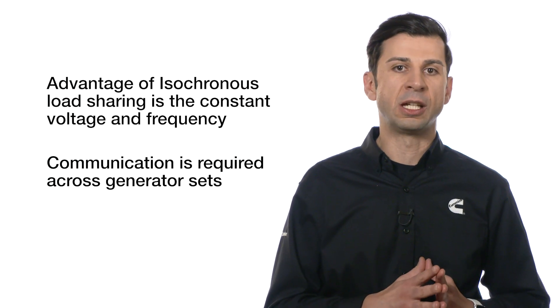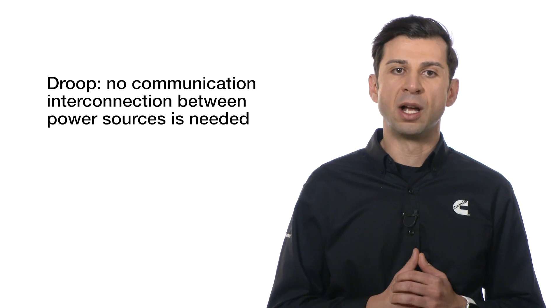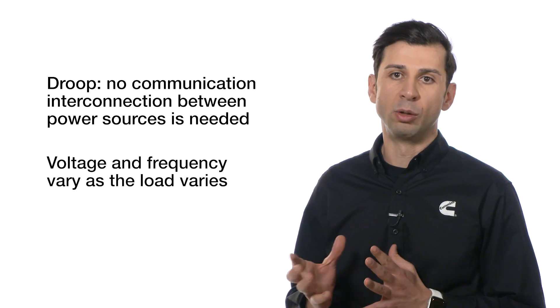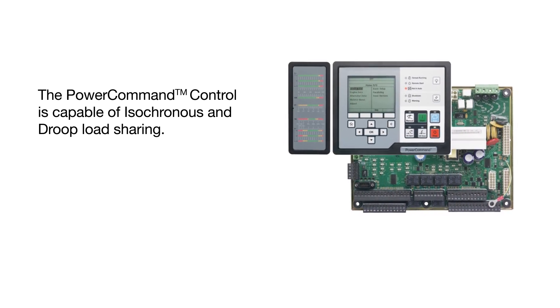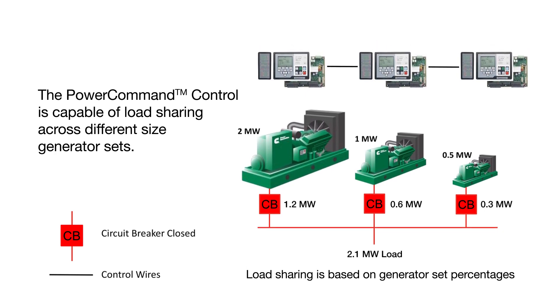However, isochronous load sharing requires the sources to communicate with each other. On the other hand, Droop does not require communication interconnection between the power sources, at the expense of varying voltage and frequency as the load varies. The PowerCommand control has the capability to do both functions — isochronous or Droop — as well as load sharing across different sized generator sets.